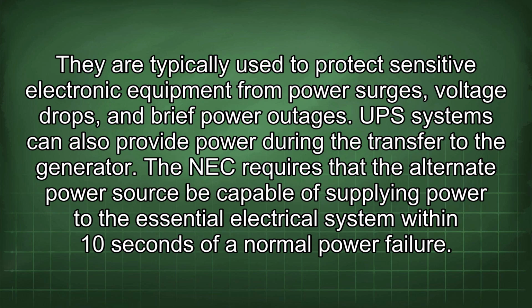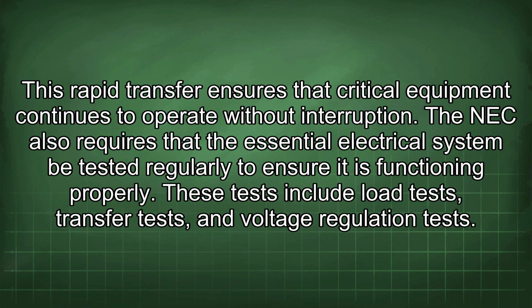The NEC requires that the alternate power source be capable of supplying power to the essential electrical system within 10 seconds of a normal power failure. This rapid transfer ensures that critical equipment continues to operate without interruption. The NEC also requires that the essential electrical system be tested regularly to ensure it is functioning properly.